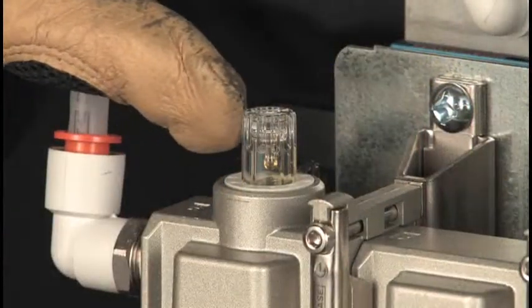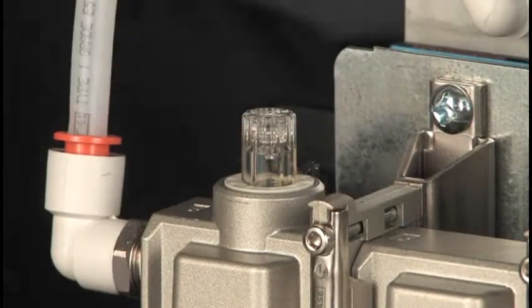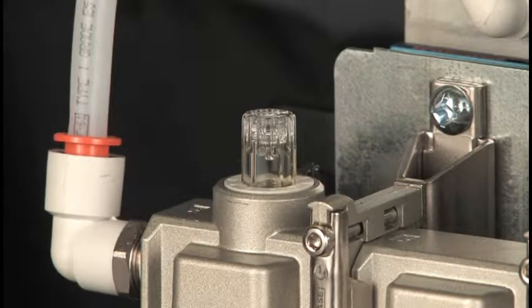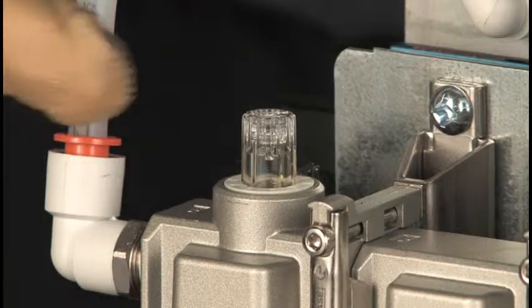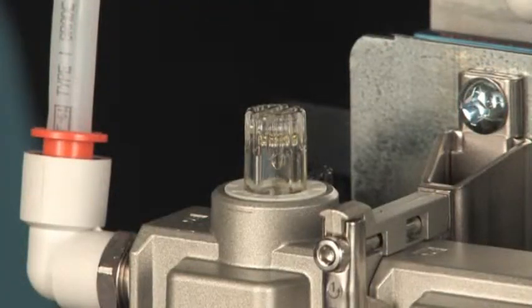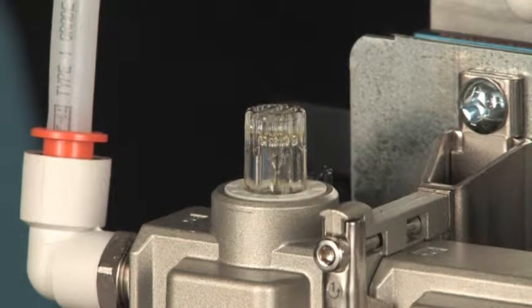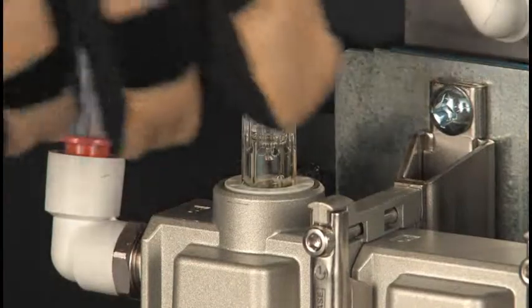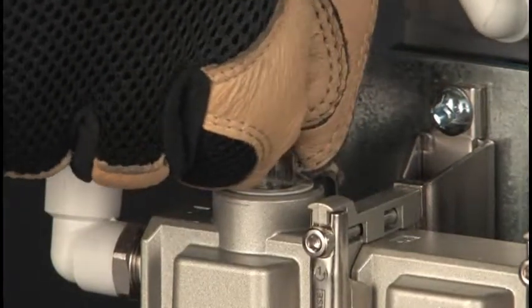Notice the small transparent knob on top. When and only when the pump is running, you will be able to see a drop of oil form and then fall into the air stream. By turning the knob in or out, you can regulate how much oil is introduced. Adjust the flow to produce one drop about every 30 seconds.